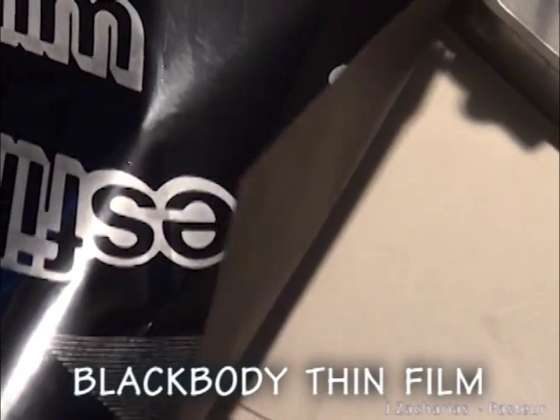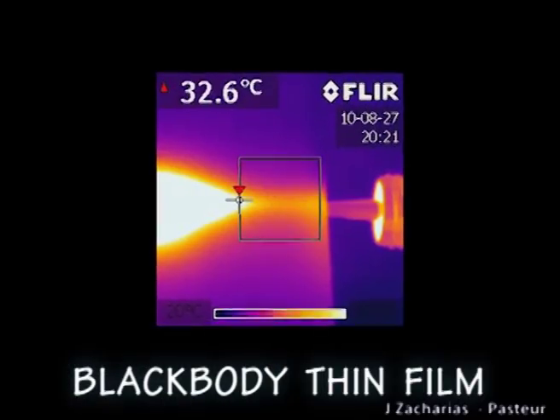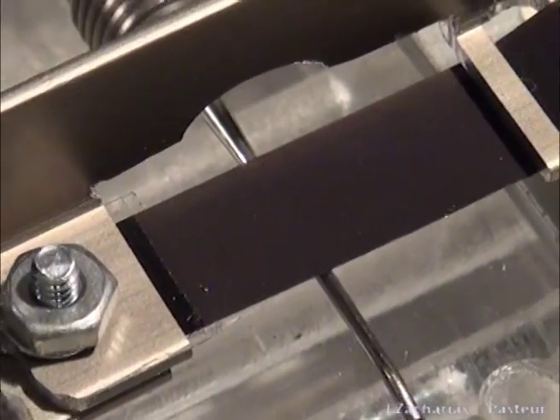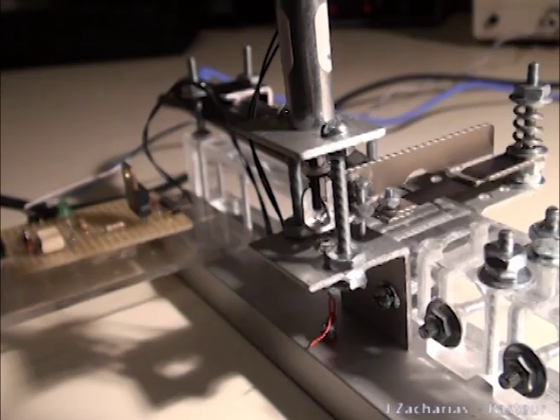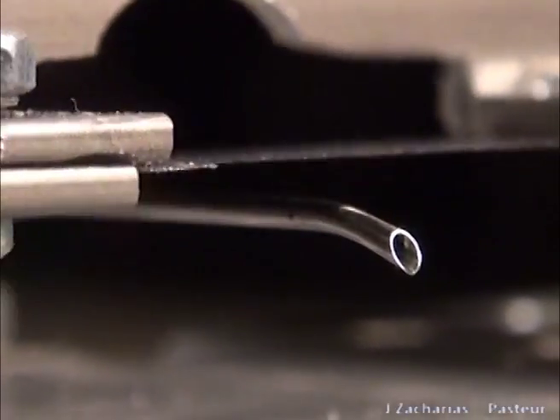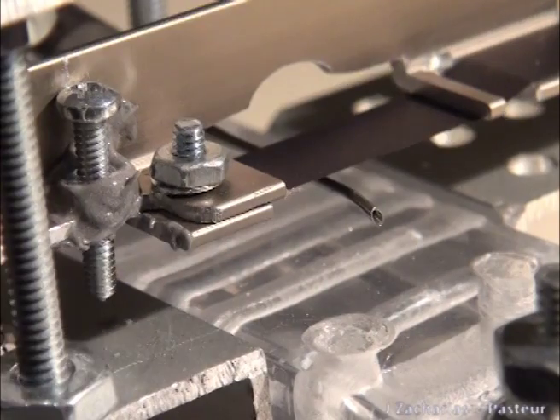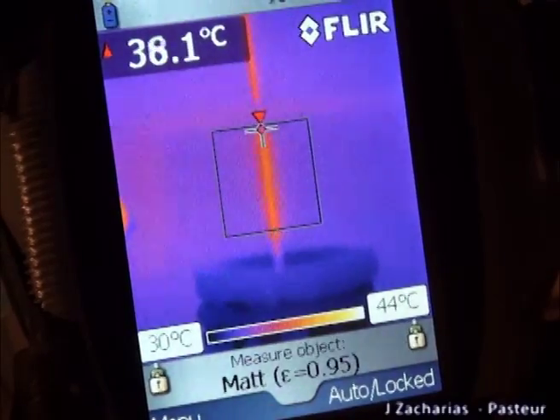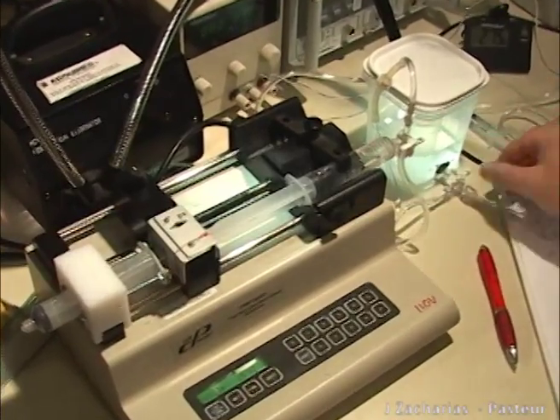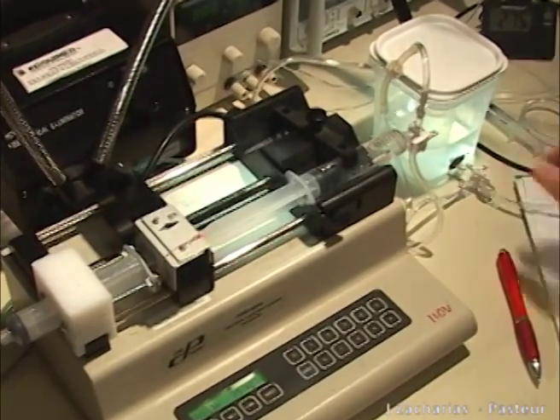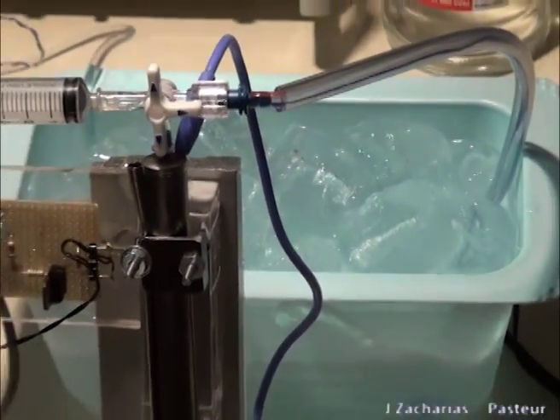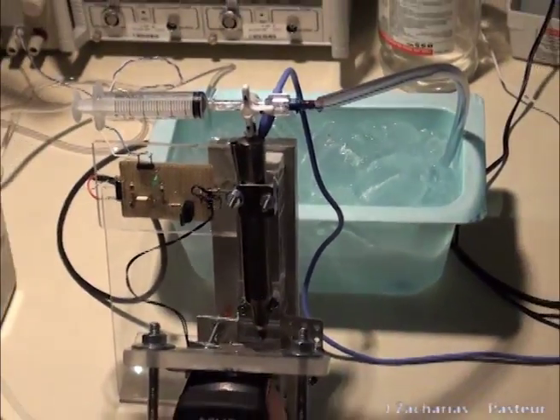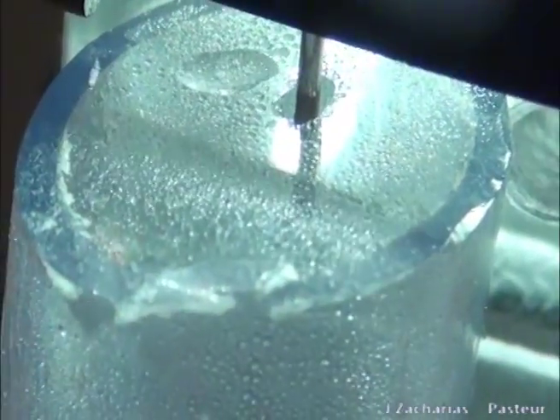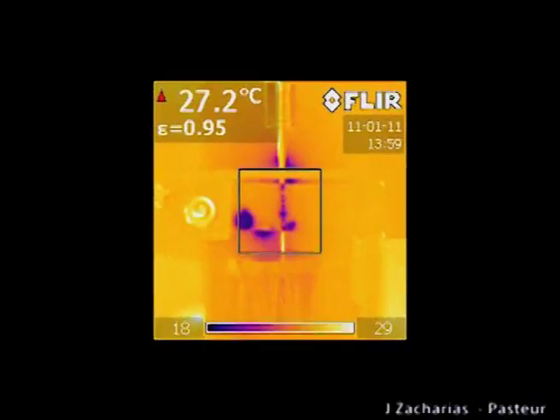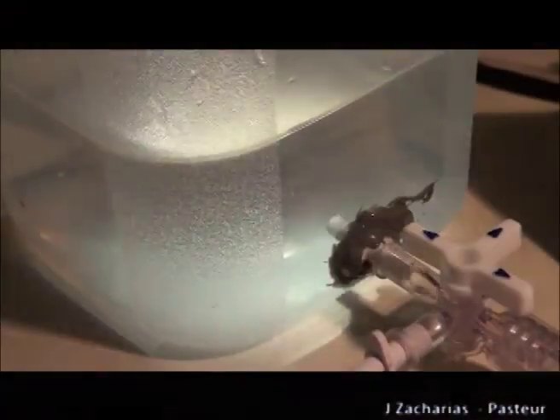A thin film with emissivity near 100% and with low thermal capacity was incorporated as a thermal screen. An electromechanic system using computer control was built to put the thin film in contact with the probe shaft only between periods of oscillation to avoid friction. A syringe pump delivered exact flow through the handpiece aspiration port. An ice bath was used in some experiments to offset inflow temperature below ambient. Water spray from the vibrating tip had to be controlled using a collector system with a perforated membrane and strong aspiration.